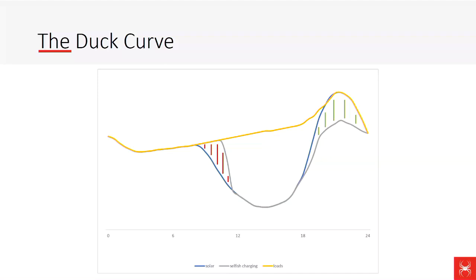But if all the batteries behave similarly, you actually make this part of the curve worse, because you're charging your battery as the sun comes up, they all reach full charge within about an hour, then go from 0 to 100% export over a 10-minute period per battery. You get some diversity so that might spread over an hour, but you still end up with a pretty significant issue, and that's with the default battery charging profile.